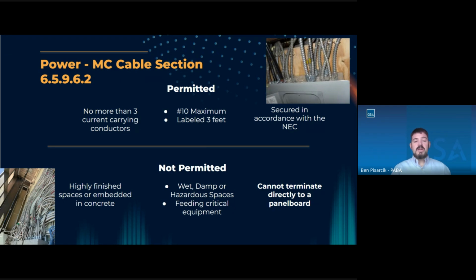And the most important there at the end, it cannot terminate directly to a panel board as you see in these photos. Conduit must terminate to the panel board and run out to the first wiring device. So that keeps your electric room nice and orderly. And then once you hit that first wiring device, whether it be a light, receptacle, or whatever it may be, then you can daisy chain, assuming it's acceptable for the space that it's in, you can use MC cable from there.